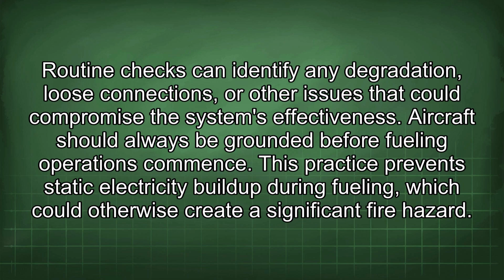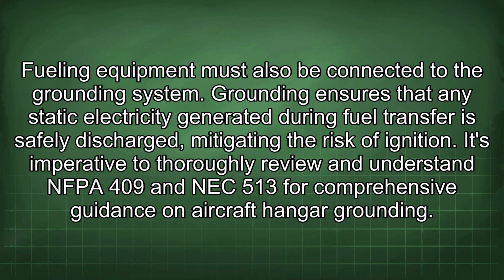Aircraft should always be grounded before fueling operations commence. This practice prevents static electricity buildup during fueling, which could otherwise create a significant fire hazard. Fueling equipment must also be connected to the grounding system. Grounding ensures that any static electricity generated during fuel transfer is safely discharged, mitigating the risk of ignition.